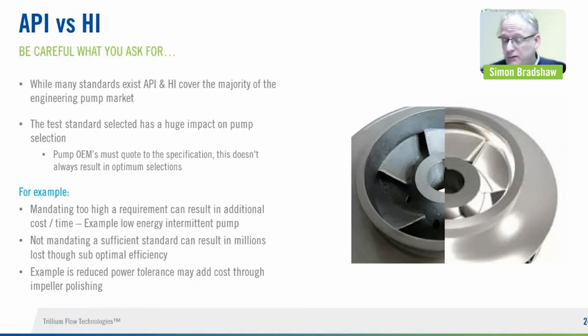On the other hand, if you have a high energy consumption process with a high power pump and it's running continuously, not specifying the right test tolerances is literally going to cost you millions over the lifespan of that equipment. And it is very important in those cases that you know exactly how your pump is going to perform on the test stand, and that you have the appropriate tolerances applied.